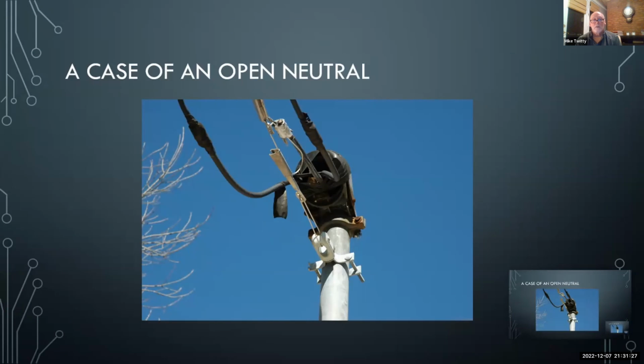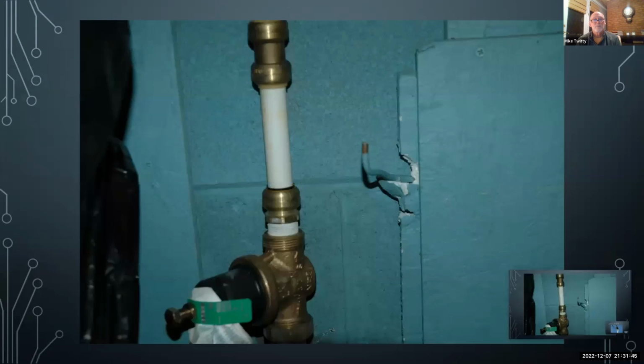This is a call out I got on. This was a squirrel had chewed through this. This is right after it had been repaired, but he chewed. They like to chew on that aluminum neutral, bare neutral, and he chewed it in two. So this home lost its neutral, service neutral to the house. As an older house, the underground water pipe was still there, but when the plumber put in the PEX, down below here is actually the old water pipe. If he just left it connected to that, he would still have a grounding electrode, but he took it loose because he was a plumber.